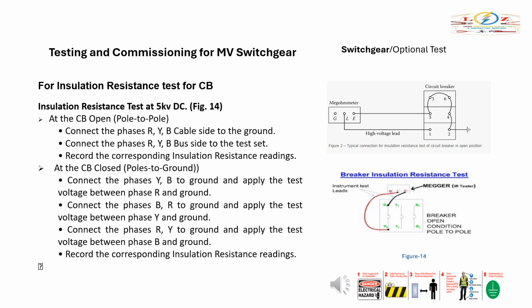For the circuit breaker insulation resistance test, test at 5 kV DC as shown in Figure 14. Perform insulation resistance tests for 1 minute on each pole, phase to phase and phase to ground with the switch closed, and across each open pole, as follows. With the CB open, connect the phases R, Y, B cable side to the ground. Connect the phases R, Y, B bus side to the high potential test set. Record the corresponding insulation resistance readings.